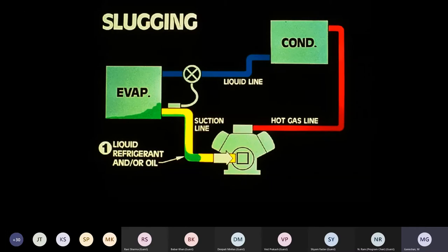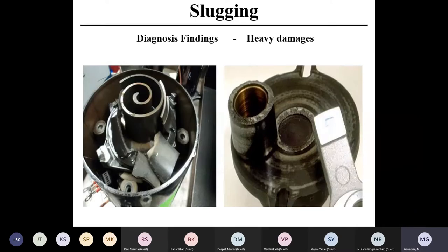Now, the third one is called slugging. What is slugging? Slugging is this: earlier the liquid, that means refrigerant liquid, used to come slowly. Now it comes all at once, liquid and oil together, in one go. That is the deadliest weapon, deadly dangerous for any compressor. Within no time the compressor can break, the piston can break, the screws can break, everything can break, because that is a heavy load for the compressor. You can see this is the real result of slugging.